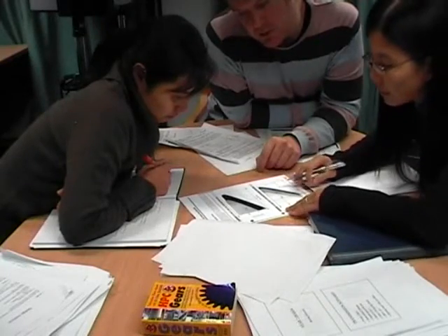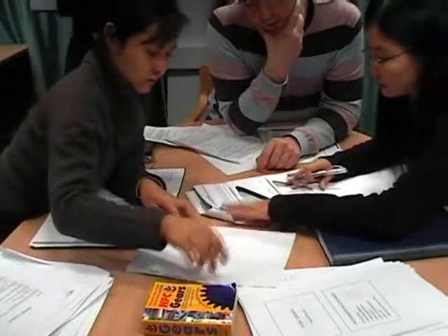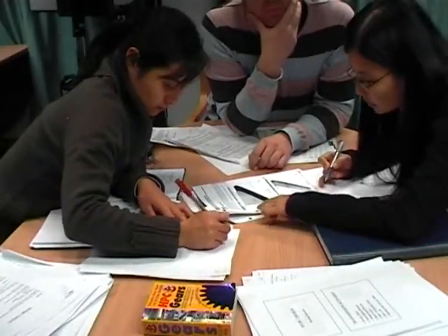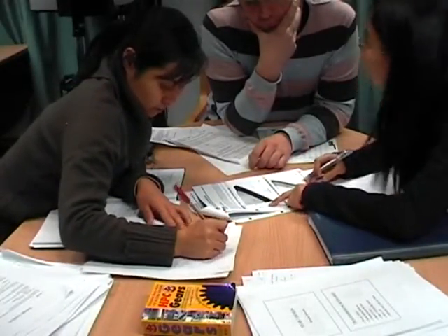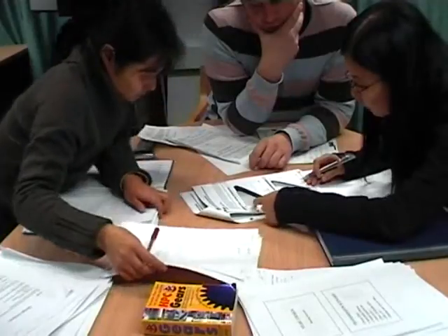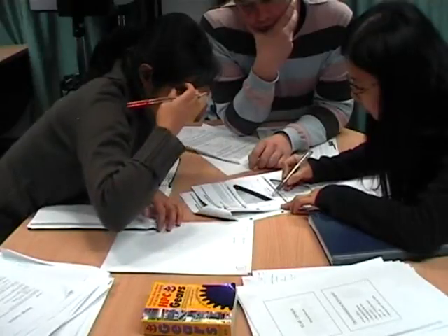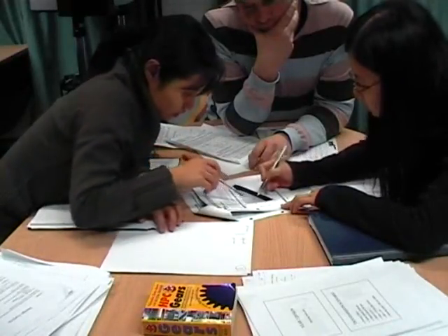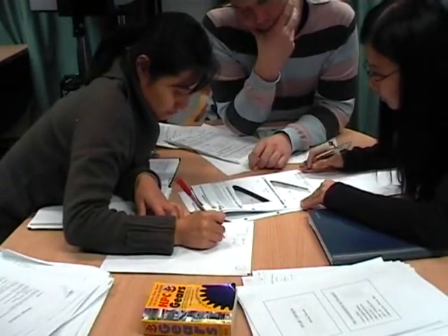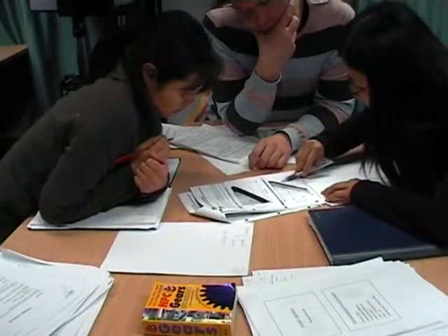Okay, determine belt pitch. The pitch is selected by speed and power. So, RPM of the faster shaft is 1,500 revolutions per minute. Our design power is 22.5 kilowatts. So we have a range of the 8M GT. This is pushing the limit, on the boundary.